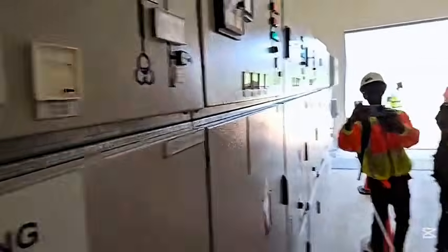This is a test run. We've powered it since yesterday, so we want to keep it like this for 24 hours to observe it and make sure that everything is okay in terms of the electrical strength, before it's logged into the grid. So these are things we're doing, and all of the equipment will go through similar steps. We do what we call the cold commissioning, then the hot commissioning, before the injection into the grid, the synchronization.